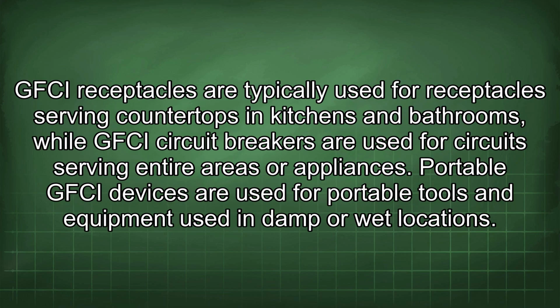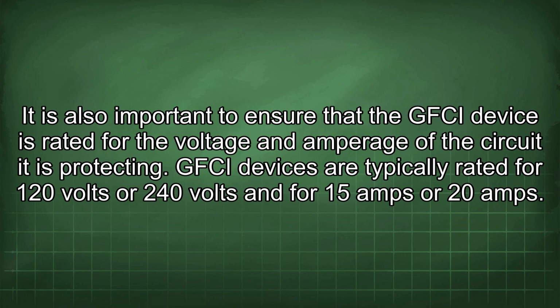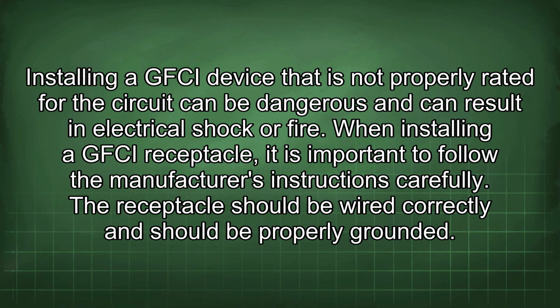When selecting a GFCI device, it is important to choose one that is appropriate for the specific application. GFCI receptacles are typically used for receptacles serving countertops in kitchens and bathrooms, while GFCI circuit breakers are used for circuits serving entire areas or appliances. Portable GFCI devices are used for portable tools and equipment used in damp or wet locations. It is also important to ensure that the GFCI device is rated for the voltage and amperage of the circuit it is protecting. GFCI devices are typically rated for 120 volts or 240 volts and for 15 amps or 20 amps.